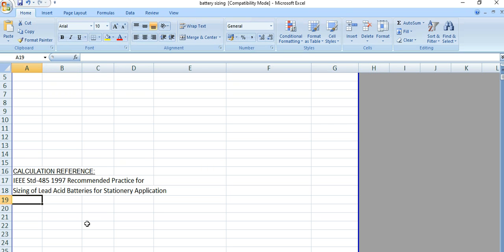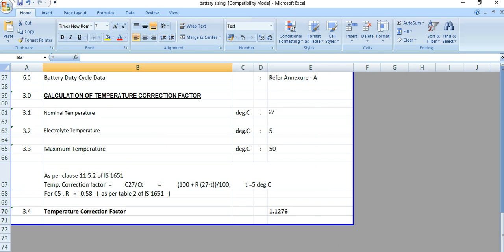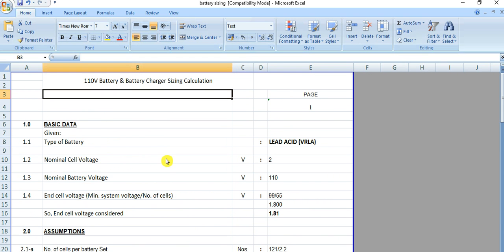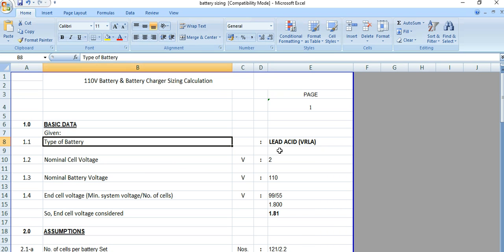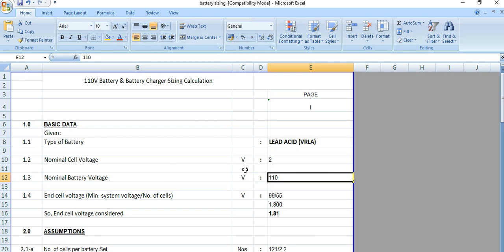I will discuss the lead acid battery sizing calculation. These are the basic input data we need. The inputs include: type of battery — lead acid; nominal cell voltage — 2 volts; nominal battery voltage — 110 volts DC or 220 volts DC as defined. The next important factor is end cell voltage (ECV).